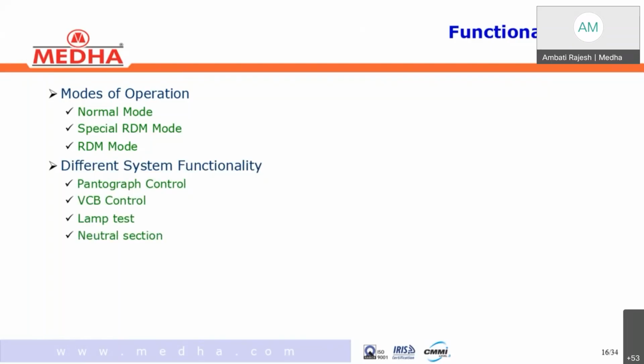The neutral section. Wherever there is a changeover from substation to substation or phase to phase, there is a section called the neutral section. Before the neutral section, there is a signboard, the 250 meter signboard. Here in three-phase MEMUs, as an operator, we have to press only the neutral section switch at the 250 meter signboard. Automatically, everything else is calculated by the system, and one by one the VCBs open, and after crossing the neutral section, it closes the VCB for normal operation.